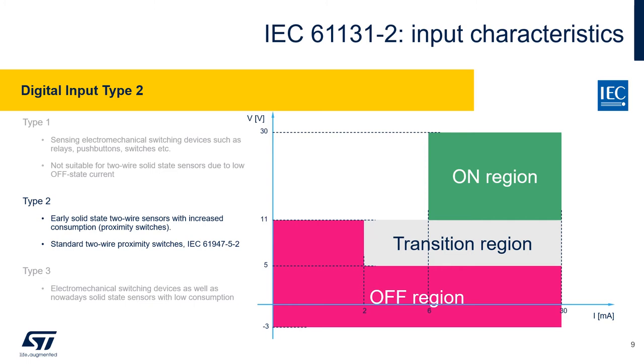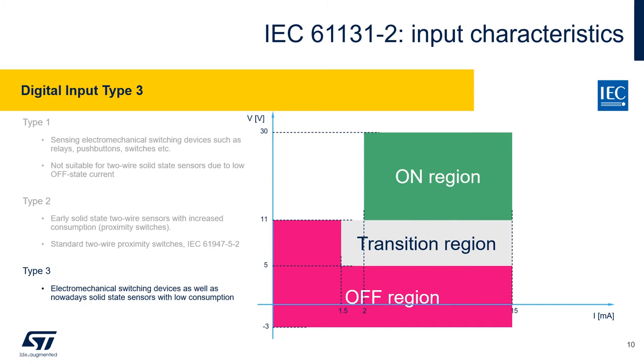Now you can clearly see the difference. Type 2 shifts the current threshold for all the regions to higher levels. The transition region starts at 2mA and the on-region even at 6mA, while decreasing the voltage threshold for the on-region down to 11V. All of this permits higher leakage current for the external switching device in the off-state, and higher voltage drop across the switching device in the on-state to ensure its proper supply. That's why this type perfectly fits two-wire proximity switches. Type 3 is a kind of good compromise between the other two — quite universal, supporting electromechanical switching elements as well as modern two-wire sensors with limited power consumption.